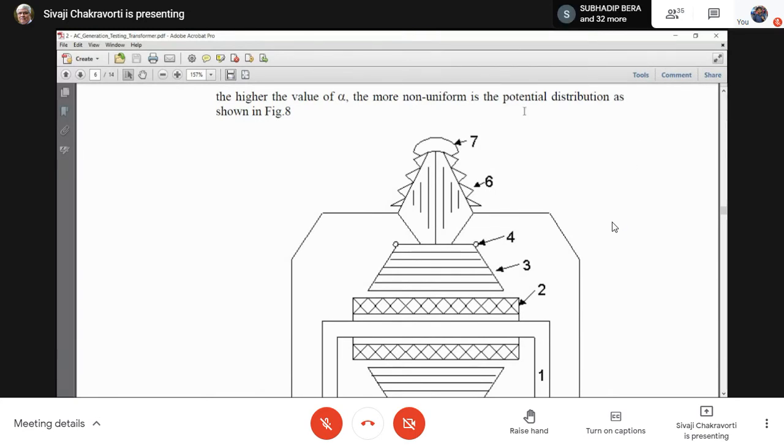Whereas here, you see, it is completely different. Here, there is no question of supporting the conductor. Here, the conductor is coming from the high voltage winding through the tank, which is a zero potential barrier, to outside. Or in other words, whenever a high voltage conductor has to pass through an earth barrier, you need a bushing.